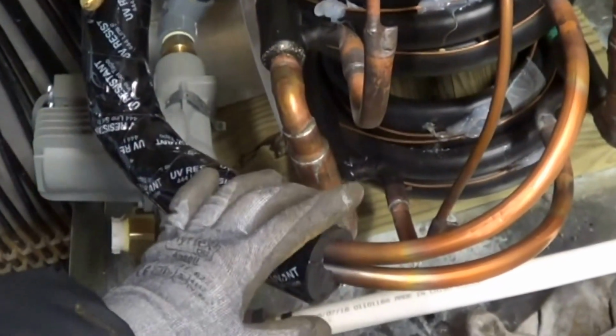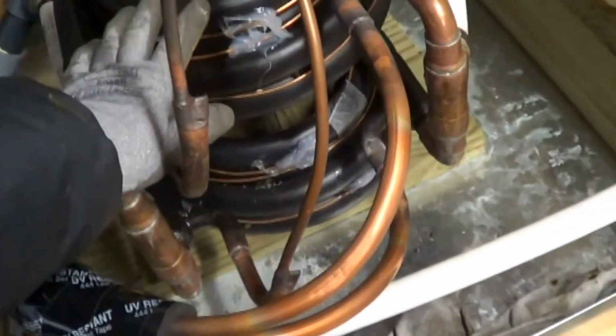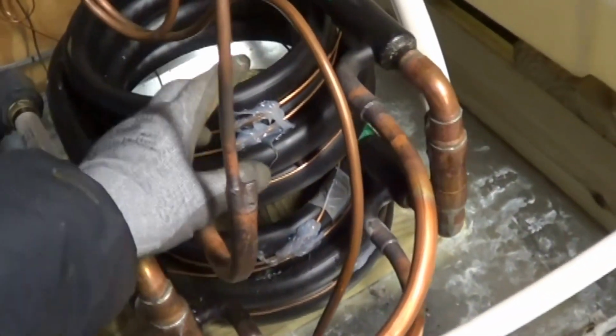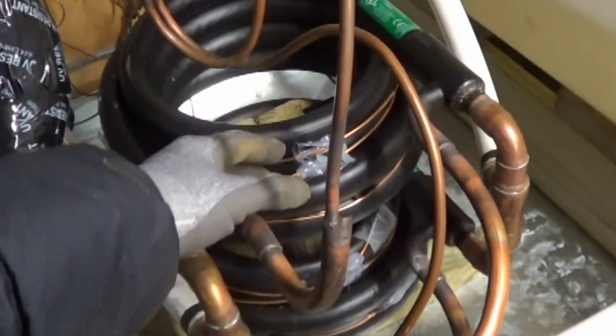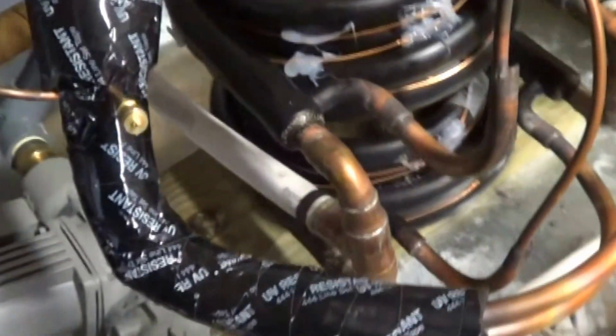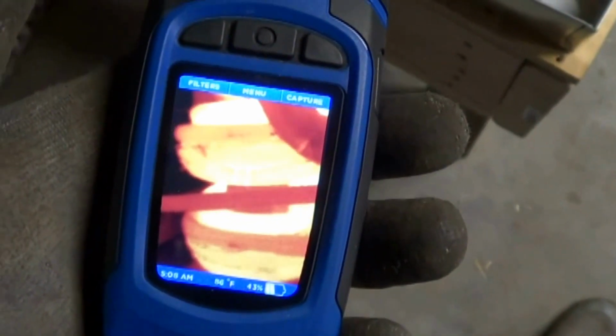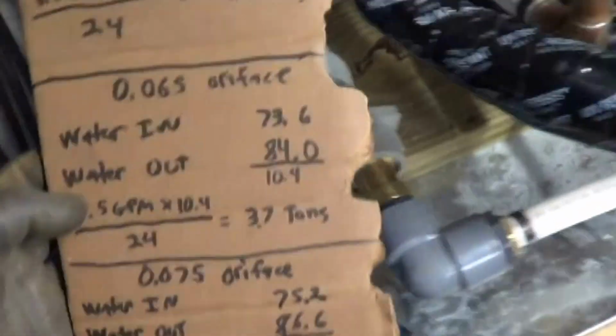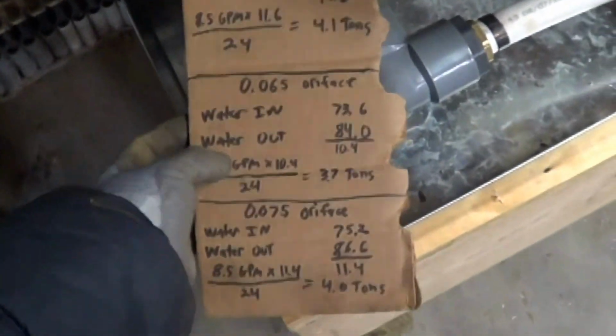When the water was 50 degrees, when the building was cold, the heat exchange works so well that you don't end up using the whole coil. So you really got to wait till it warms up before you can see the whole coil being used. So I tried some things on capacity. We got some numbers here.